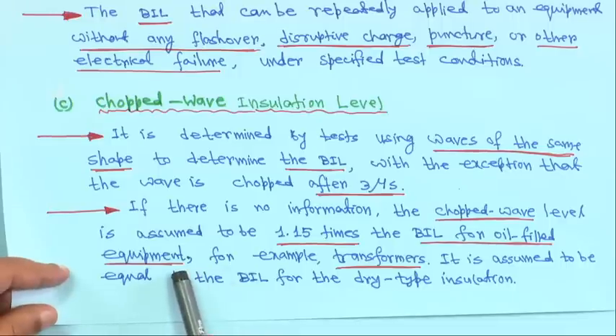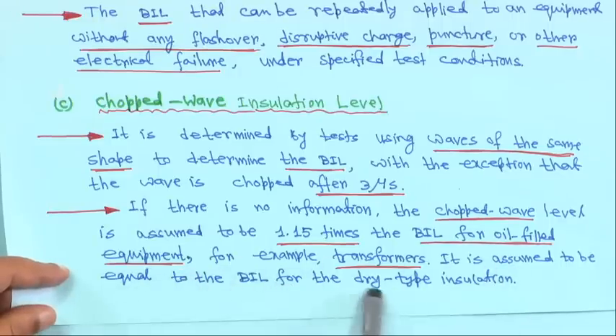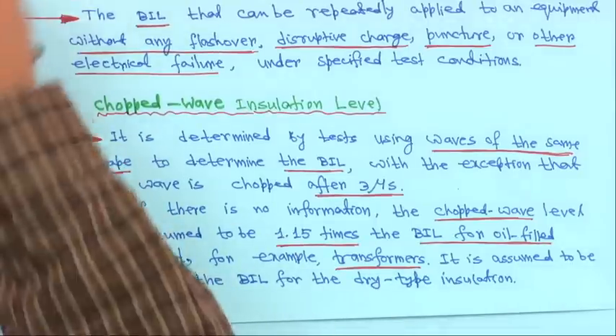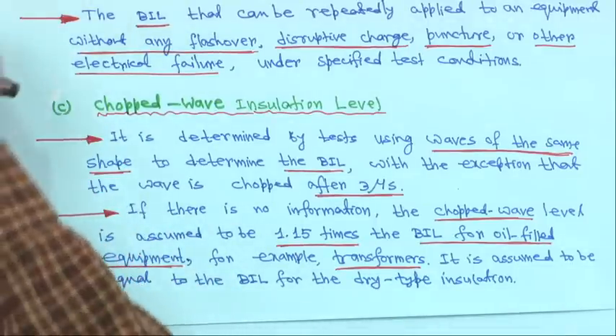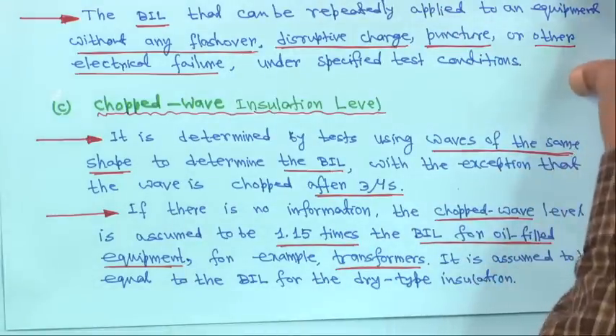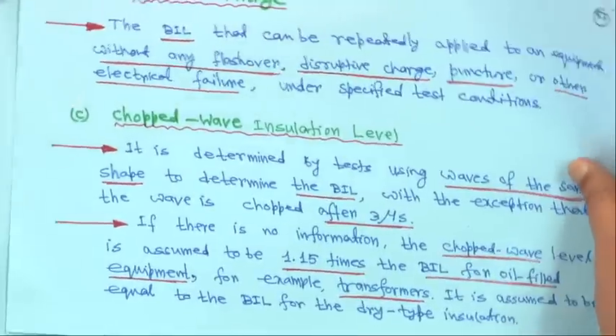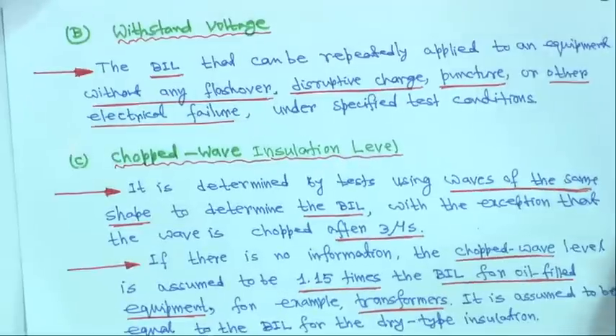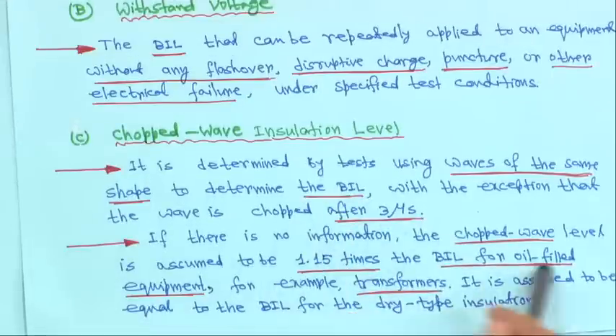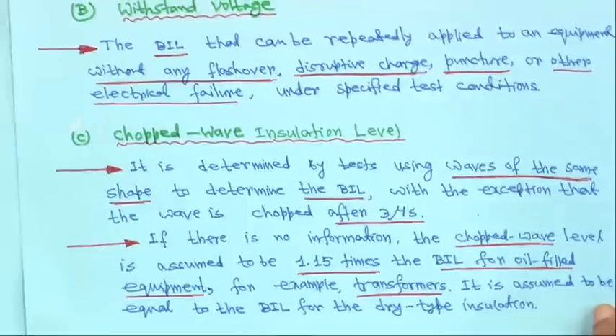If there is no other information, it is assumed to be 1.15 times the BIL for dry-type insulation. Similarly, 1.15 times the BIL is assumed for oil-filled equipment, such as transformers, for the chopped wave test level.